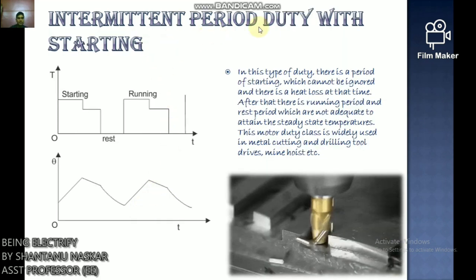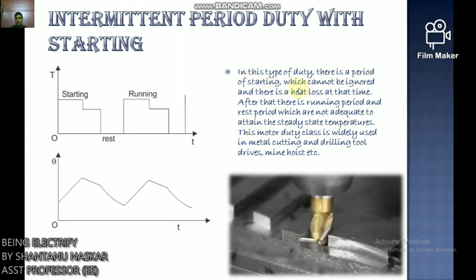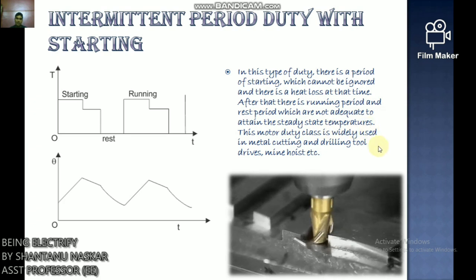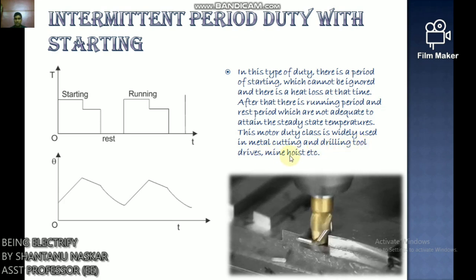Intermittent periodic duty with starting: There is a starting period that cannot be ignored, with heat loss during starting. After that there is a running period and rest period, neither of which is adequate to reach steady state temperatures. This duty class is widely used in metal cutting and drilling tool drives, and mine hoists.